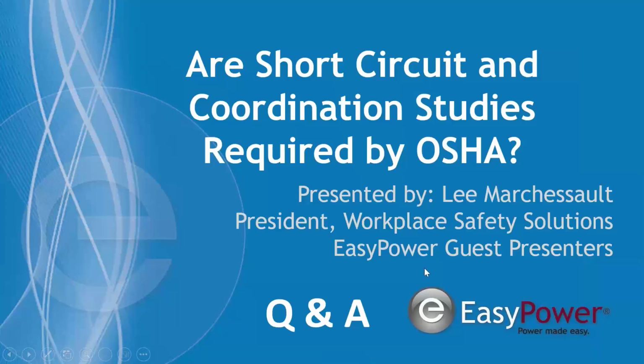There is another question here from Harold, and he's saying, does it mean if I want to correct an issue with the number of main lug only panels in line, I can interrupt the feeder to those panels with a correctly rated fuse disconnect instead of a main breaker, which cannot be mounted after the installation? Yes, you certainly can. I mean, sometimes main lug panels come off of main distribution panels. I don't have any big preference. The good thing about having a main breaker in a panel is that it lowers down the arc flash level on the bus work. The feed coming in is still going to be the same level as it would be whether it's a main disconnect switch or a main lug. You certainly can do that for sure.